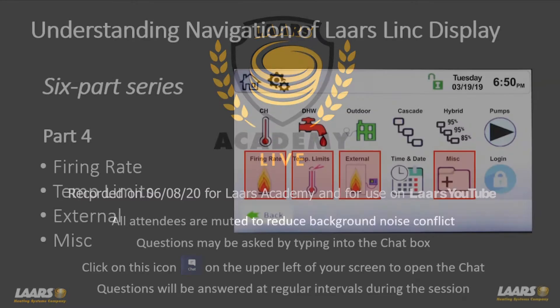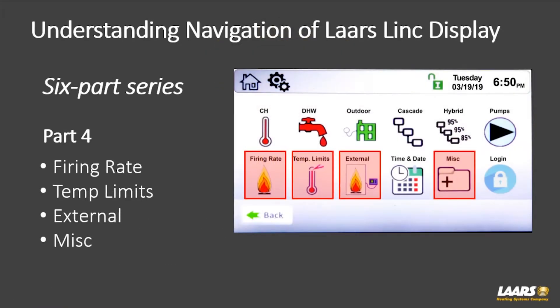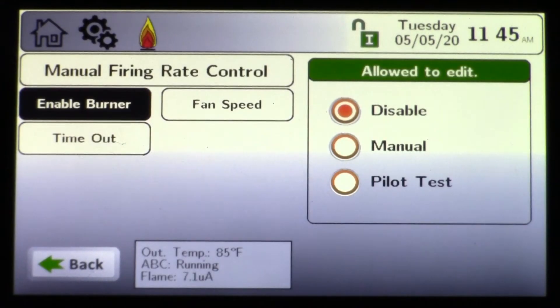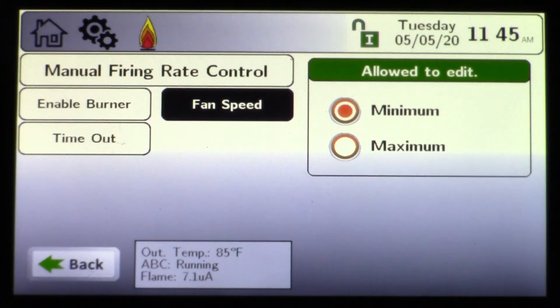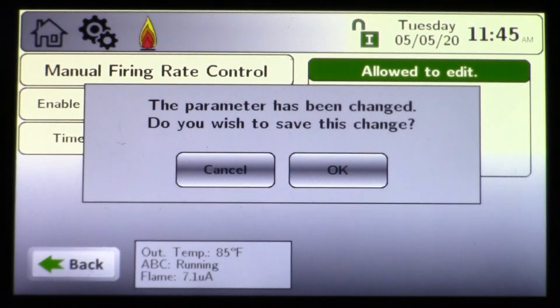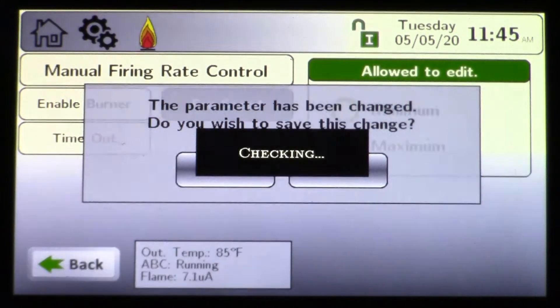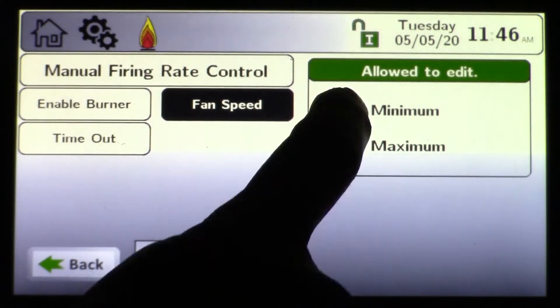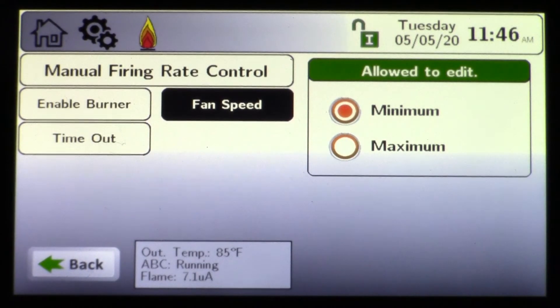Here in part four of the series we'll look at firing rate, temp limits, external, and miscellaneous. We'll start with firing rate — this is for combustion setup. In this example, for a Magnotherm 5:1, you can choose minimum or maximum, and that'll modulate the boiler to 100% or 20%. Once I chose maximum and clicked okay, the modulation goes right to 100%. Minimum fire will modulate down to low fire, which is 20% on the Magnotherm 5:1.